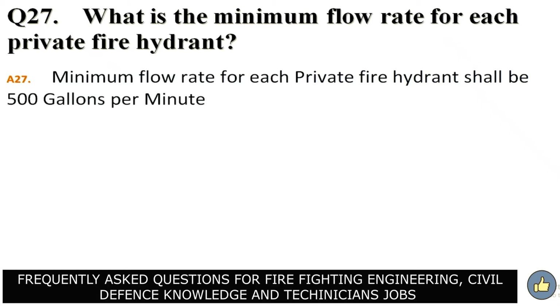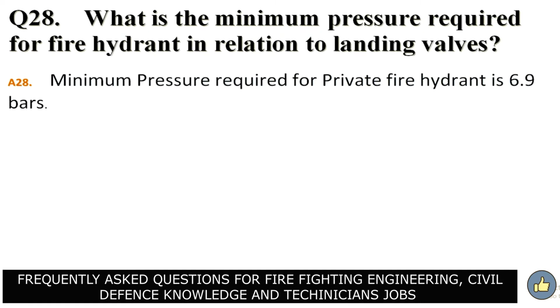What is the minimum flow rate for each private fire hydrant? Answer. Minimum flow rate for each private fire hydrant shall be 500 gallons per minute. What is the minimum pressure required for fire hydrant in relation to landing valves? Answer. Minimum pressure required for private fire hydrant is 6.9 bars.